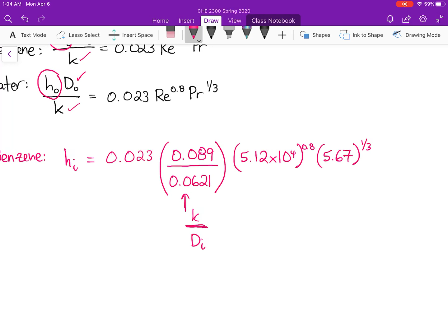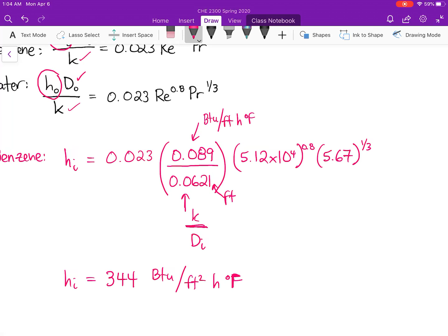If I do my algebra correctly, I should get a convective heat transfer coefficient on the inside of my inner pipe of 344 BTUs per foot squared hour degrees Fahrenheit. That makes sense: the units on K are BTUs per foot hour degrees Fahrenheit, and dividing by a foot gives BTUs per foot squared hour degrees Fahrenheit.